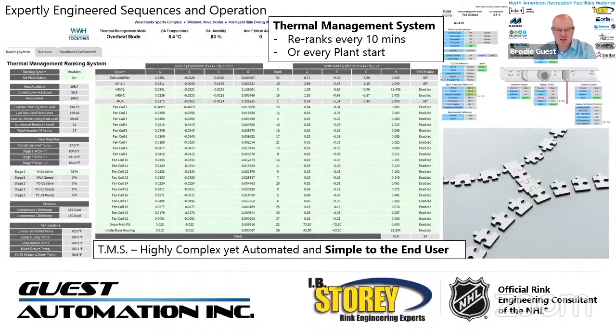This causes far fewer starts and stops of equipment and cycling. Each major piece of equipment, shown in green, is enabled to run and is ranked based on its heat load and when it will effectively serve again.